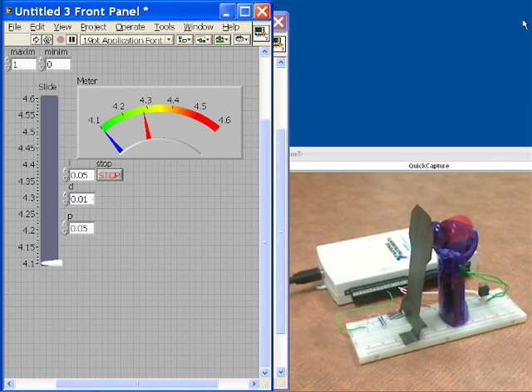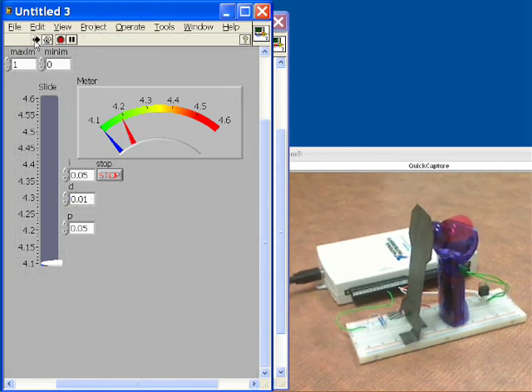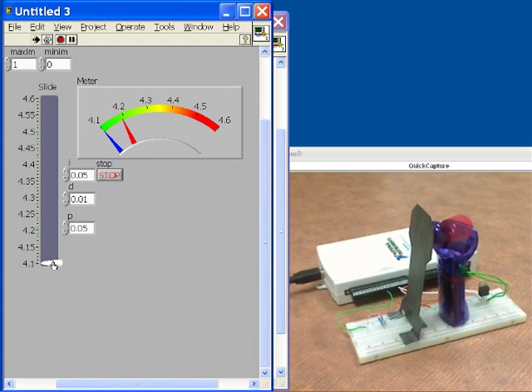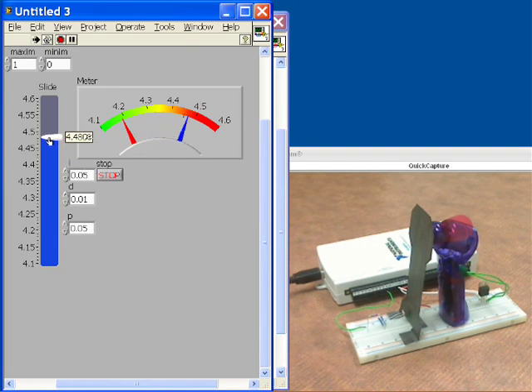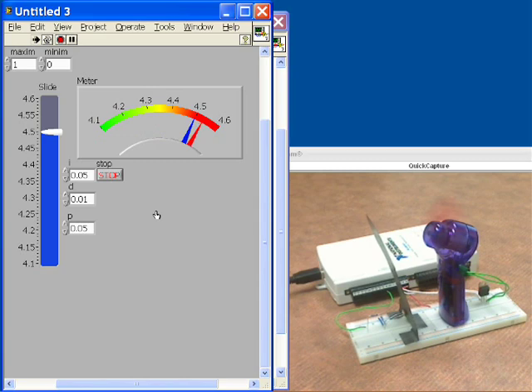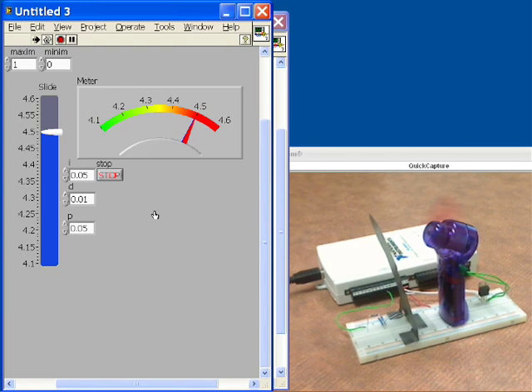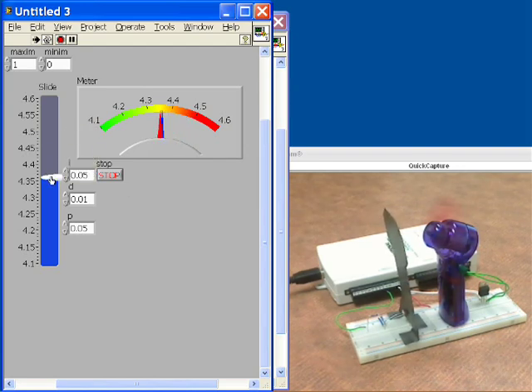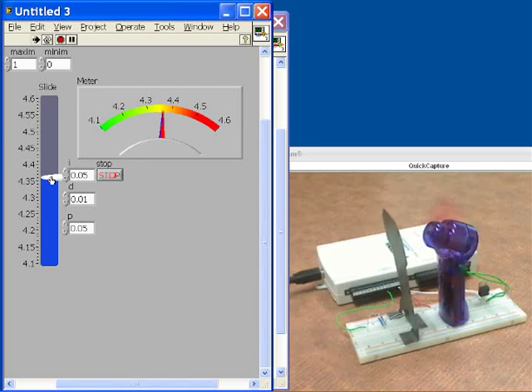So at this point we're ready to click the run button and see this work. So at this point we see the deflector default value is at 4.2 and we're below that so it can't go any lower than that. We're going to take our set point up to about 4.5 and we'll let it stay there. And at this point the deflector will begin to move and it seeks the value it knows. It's outputting just a little too much now so it'll let off and it zeros in on that 4.5 pretty accurately. Let's go ahead and drop it down to about 4.35 or 4.4 in that range. And then we'll see that the fan decreases. It zeros in and it holds it pretty accurately there as well.